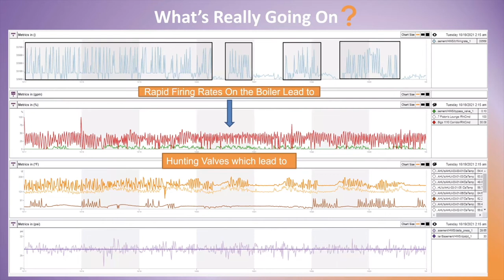In the next slide, we'll show what's really going on. It's a bit complex, but the top chart shows rapid firing rates from a boiler, not an air handler. Beneath that, it helps us derive that we're seeing inconsistent valve hunting, where the heating valves are going up and down. That's the red line. Again, squiggly is bad.